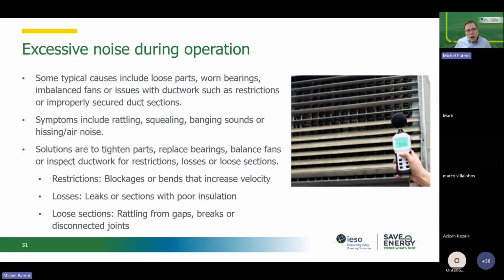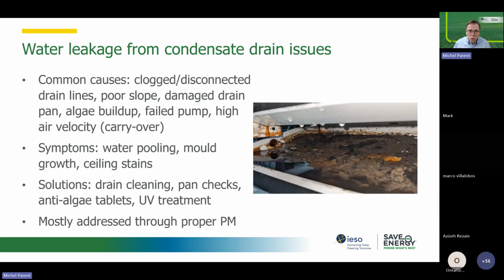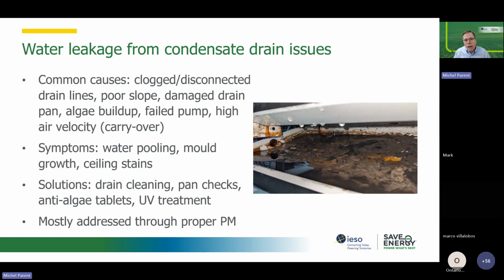Obviously, there are other reasons such as leaks. On that aspect, the one thing I want to mention, I think we do have that later on. Most buildings, 70% of commercial buildings, have high leakage from their distribution system. And when I say high leak, it's 10 to 30% of the air that you send in your ductwork that is lost. Often it can be lost through small openings, and if your pressure is high enough in your ductwork, it will create a noise issue. So don't think that 100% of the air going into your ductwork gets into the space. On average, it will be 70 to 90%. And you can test that. Again, it's not something you would do as part of a PM program because it's too much work, but you would do it as part of a recommissioning, where you would check the leakage from your ductwork, and then there are solutions to that, but they're more capital intensive.